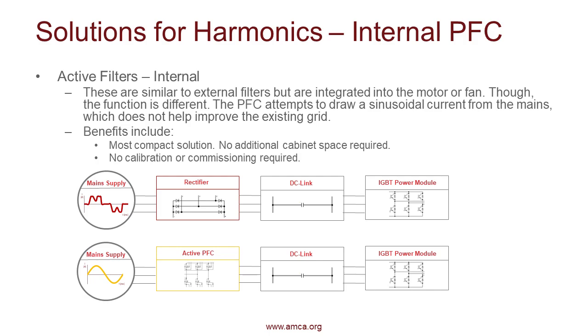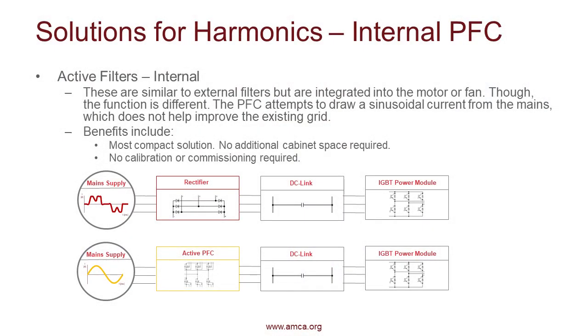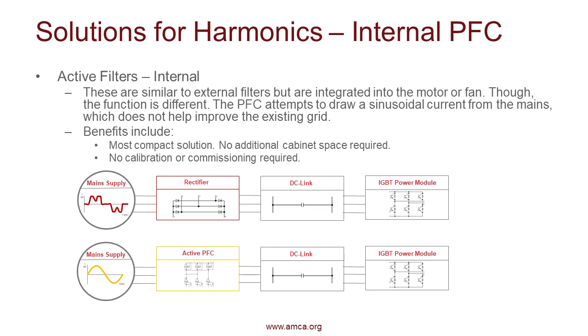So unlike the passive filter and the active filter, this is all housed inside your motor or your VFD. So it's different in the sense of you have no extra wiring, you don't have to find space inside your cabinet, it's just already built within your motor. So we have the example we talked about earlier with the rectifier, the DC link, and the IGBT power module. Now we're looking at the rectifier becoming an active PFC. So this is a series of switches that is helping bring in a more ideal sinusoidal wave to the fan, and thus helping reduce your harmonics.